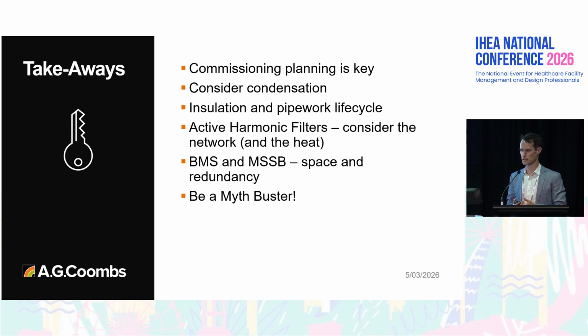Consider condensation in plant rooms, and obviously don't run any pipe work above electronic equipment, regardless of whether it's insulated or not, because at some point you could get tracking of condensation on that pipe work.